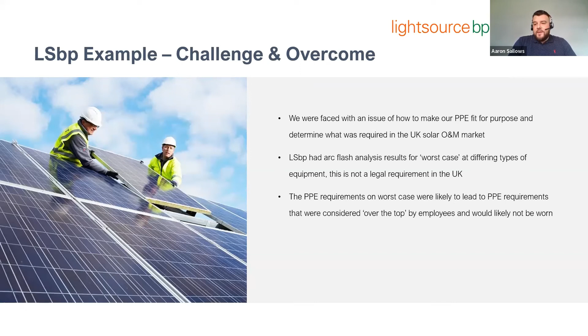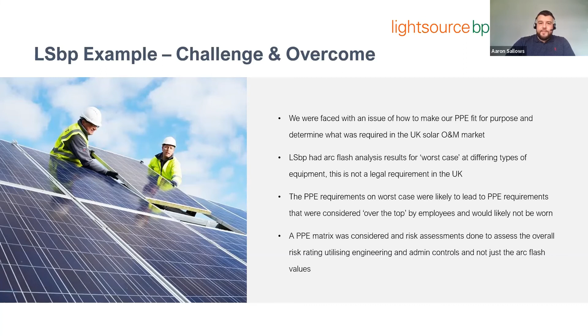So our approach was to pull together a PPE matrix and carry out specific risk assessments to assess the overall risk rating - similar to what Jonathan was talking about earlier, looking not only at severity but also likelihood and other control measures such as engineering and administrative controls. For example, hierarchy of switching: if somebody's standing in front of equipment, can we implement remote switching to remove them from the switchgear as much as possible? We consider all of this, plus administrative and procedural processes, before relying on PPE, trying to make PPE the last line of defense to catch anything that might go wrong if engineering or admin controls fail, so it can protect the people carrying out the work.